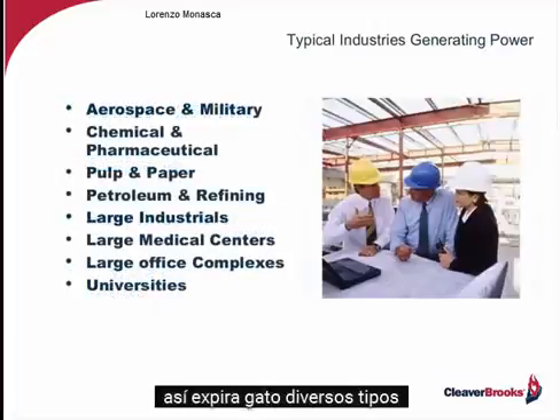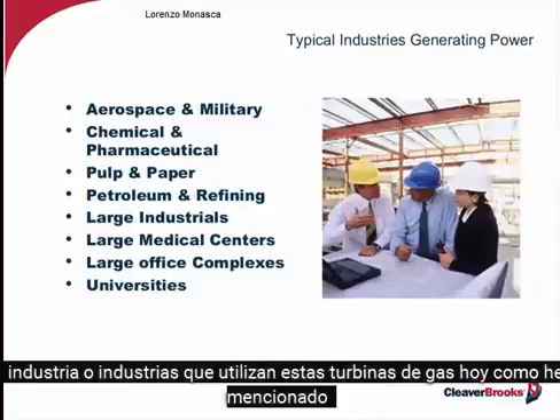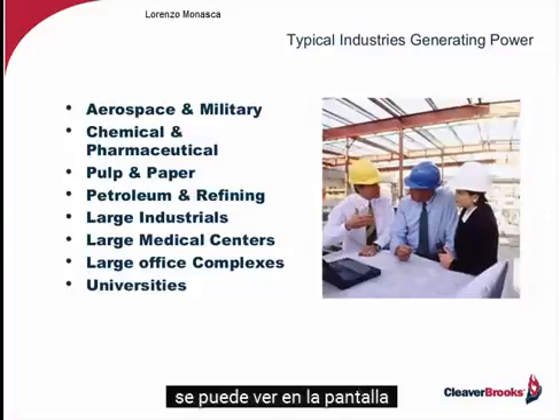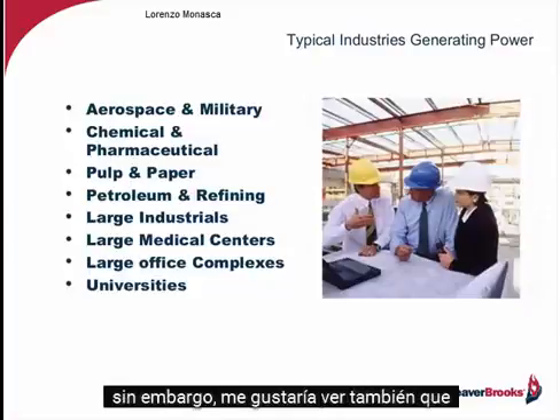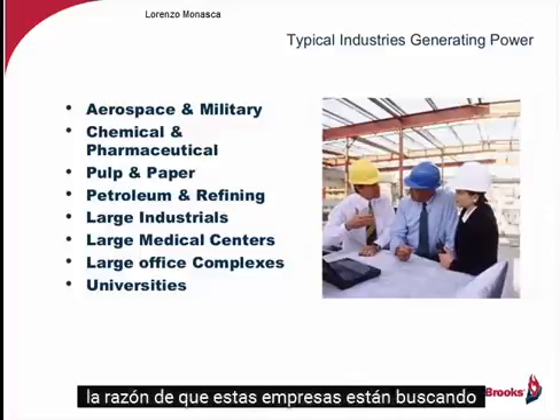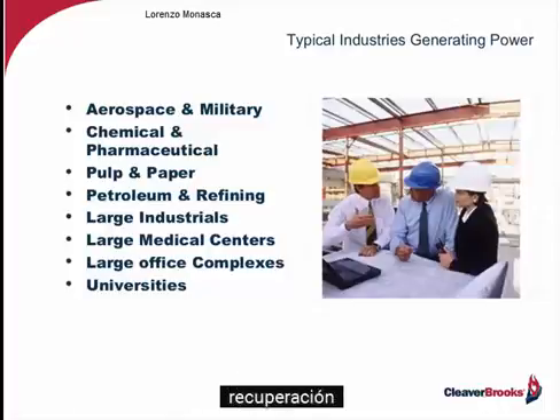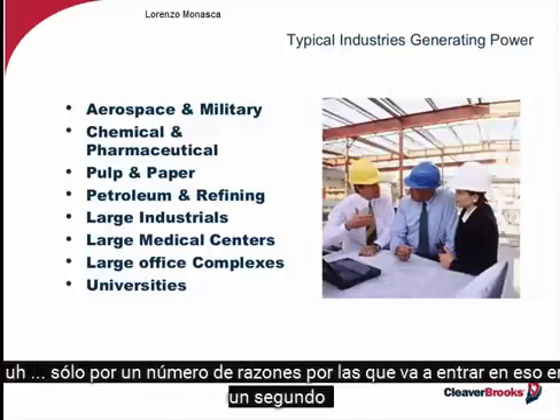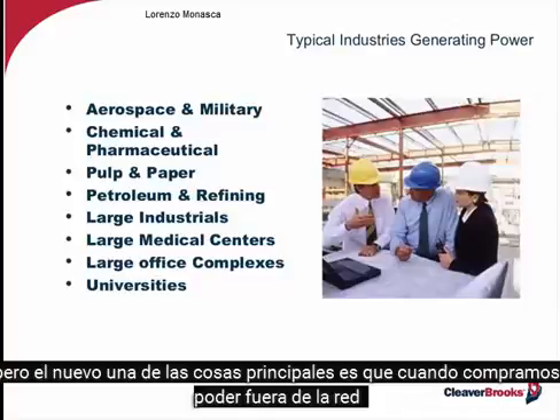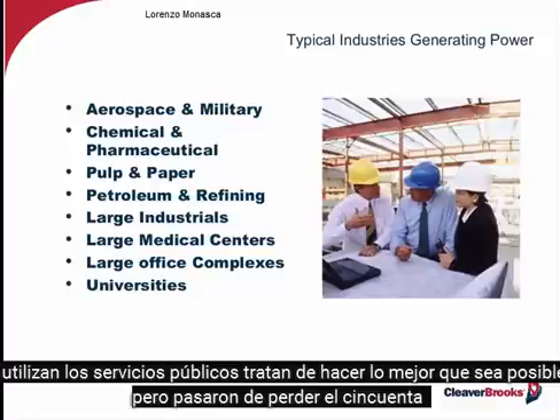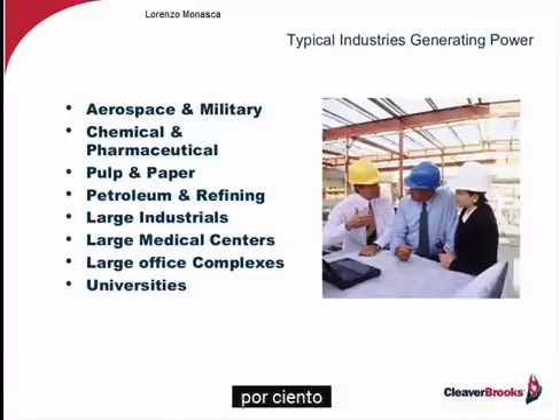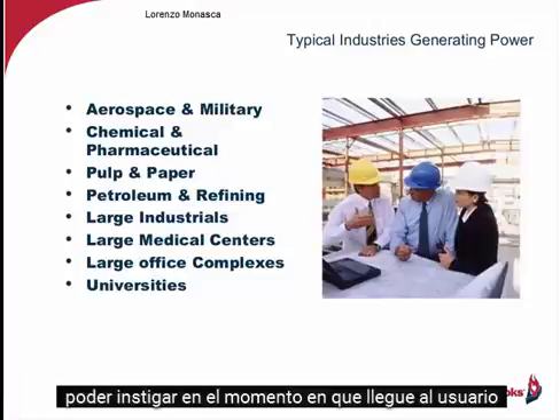Now, as far as the various types of industries that are using these gas turbines today, as I mentioned, you can see them on the screen. And I might say also that the reason that these companies are looking at this type of recovery, the combined heat and power, is for a number of reasons. We'll get into that in a second. But one of the main things is that when we buy power off the grid, these utilities try to do the best they possibly can, but at best we're losing 50% of that power by the time it gets to the user.